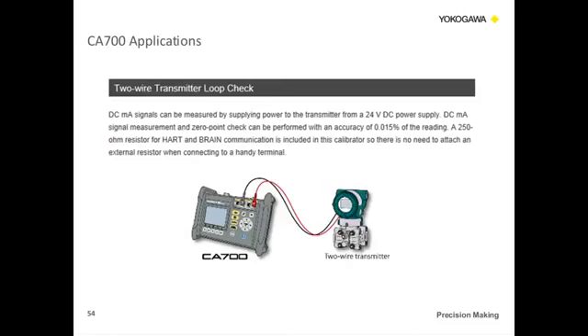2-wire transmitter loop check. We're going to supply the 24-volt DC power, measure the milliamp signal, and do the 0-point check from a transmitter. We also provide the 250 ohm resistance that will help you when you're connecting with a handheld communicator, whether it be HART or BRAIN. We need that additional load in the loop, so the CA700 can provide it.